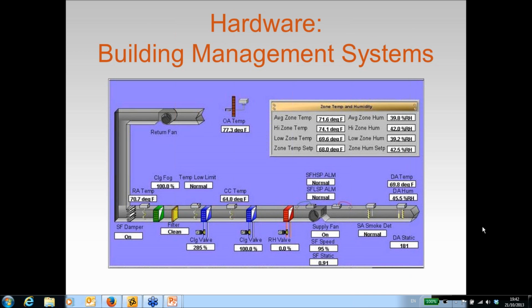So we talked about the hygrometers, we talked about the hygrothermographs, and now I'm going to jump to the other end of the technological spectrum, where we have the building management systems, or BMSs. BMSs are computer-based control systems installed in buildings, and they control and monitor the building's mechanical and electrical equipment, such as ventilation, lighting, power, fire, and security systems. Building management systems are most common to larger buildings, and the systems linked to a BMS typically represent 40% of a building's energy usage. And if we include lighting, the number approaches 70%.